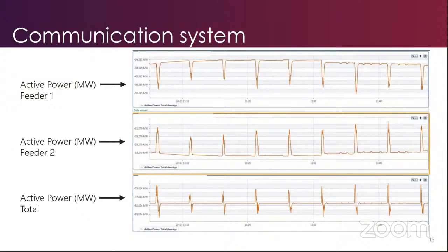As you see in the middle plot, this battery has two feeders. The middle one shows it was charging at this time, and each spike shows the disconnection of part of the inverters. The top figure is from the other feeder, trying to compensate for the loss of charging from the first one. But overall, this results in a spike, which is not desirable in operation.